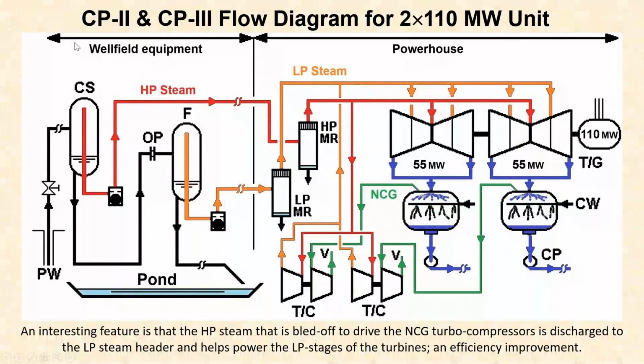Again, the flow diagram. Remember, one of these arrangements is sitting at every production well, both for units 2 and 3. And the turbine is here, tandem compound, low-level condensers. Notice the non-condensable gases, which have to be removed because you get CO2 and H2S, perhaps some other things mixed in with the steam. So you pull them off, and normally you just use a steam jet ejector, but in this case they use turbo compressors. Here's the compressor that sucks the gas out and discharges it through a vent. And that compressor is driven by a small steam turbine, which gets its steam from the high pressure header. But after it's used, they don't simply dump it into the condenser; they return it, still under pressure, to the low pressure steam header where it can go through the turbines and generate some more electricity. That's a novel feature and it is an efficiency improvement. Next.